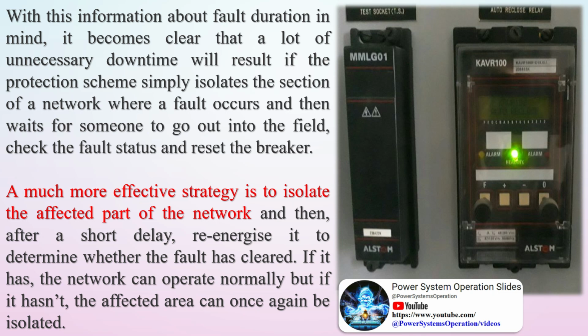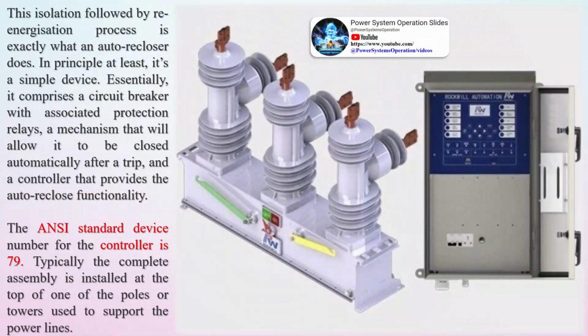The action time is started with the start of the fault detection. An AR cycle is only started if a trip command is issued before the action time has elapsed. Dead time: minimum time required by the relay for the reclosure of the circuit breaker once the CB is tripped. The time is started once the circuit breaker operates. Reclaim time: minimum time for the successful completion of the auto-recloser cycle and circuit breaker closing.